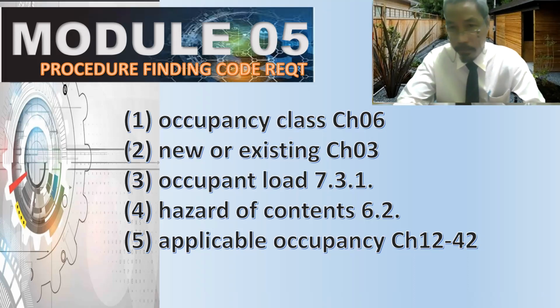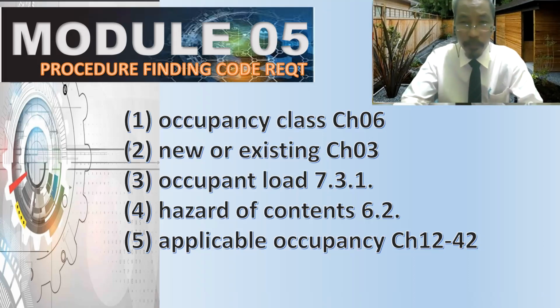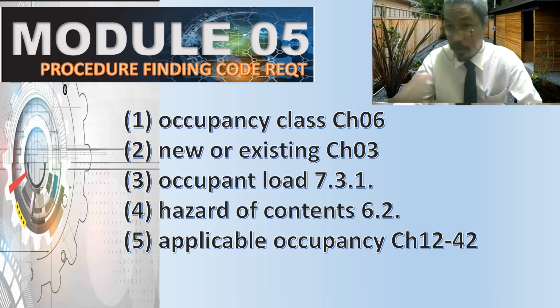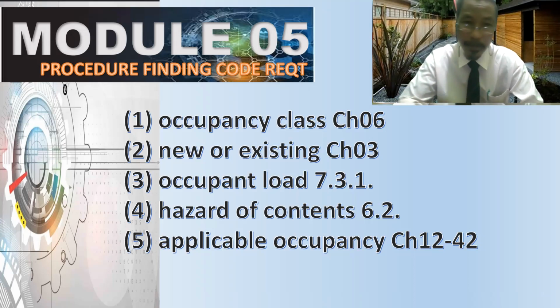The third step is to look at chapter 7, specifically section 7.3.1, wherein there is a definition for occupant load: how to compute occupant load for each and every occupancy classification and existency, meaning new or existing.